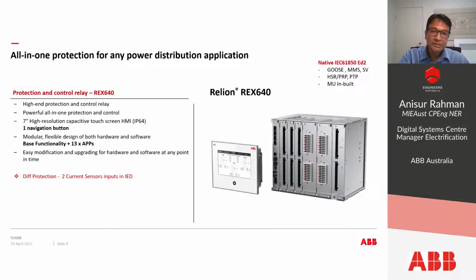The main driver to use this relay is that differential protection needs two current sensor inputs, and this relay has two current sensor inputs, and we get a lot of other benefits as well. This relay has a modular and flexible design, for hardware and software. The software comes with base functionality, which includes all the voltage, current and frequency protections. In addition to that, it has 13 apps, like mobile apps. Whenever you need, you can download any app for any protection function and it is ready to go. It also comes with a 7-inch high resolution touch screen HMI, with only a single navigation button.